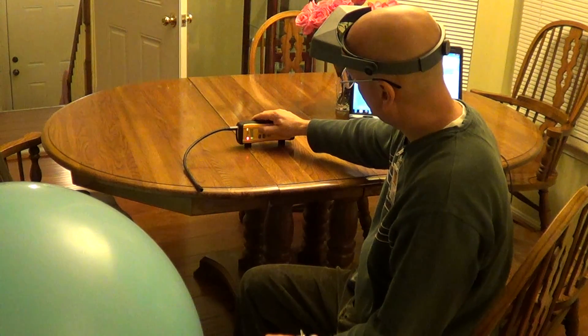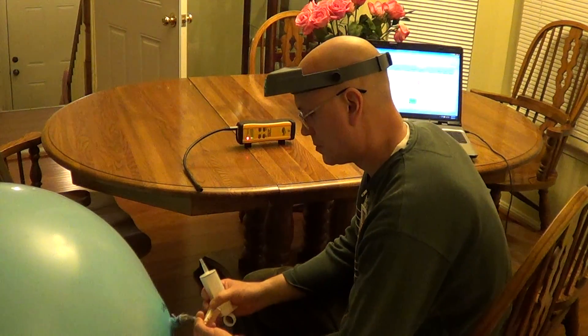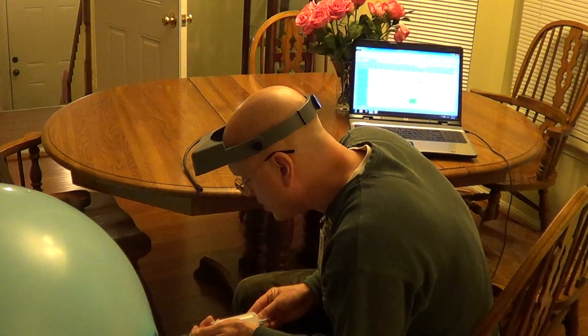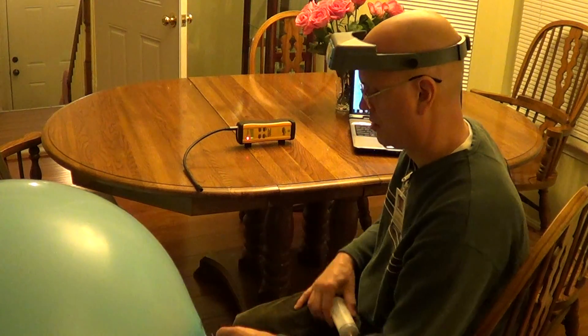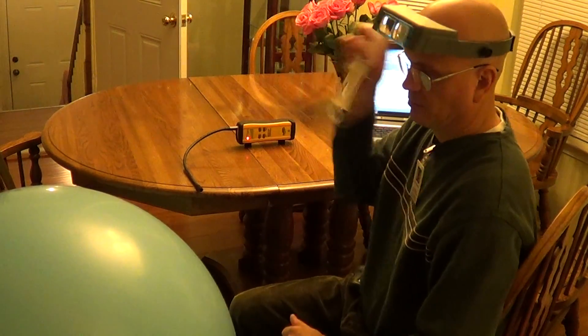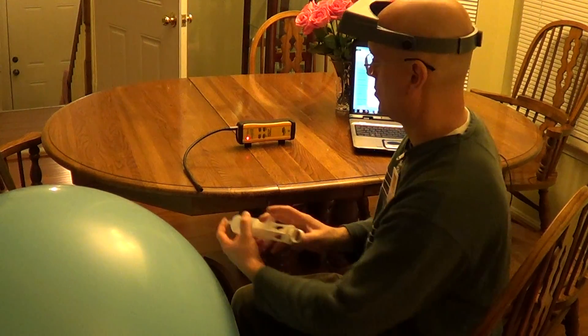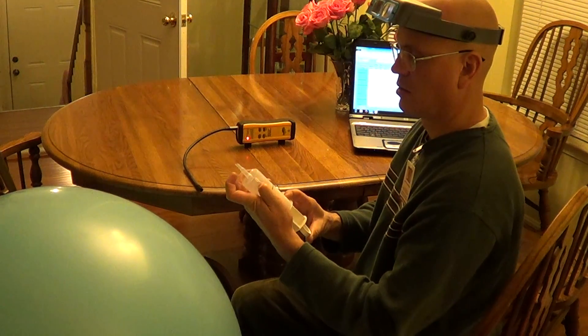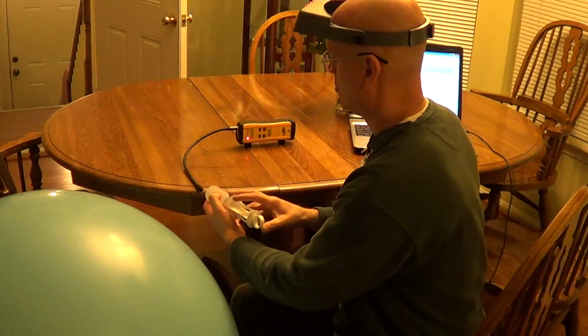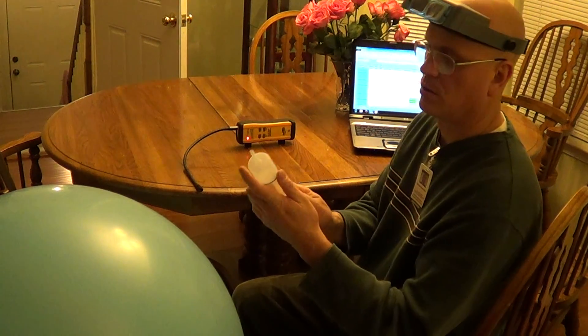Let's go on manual mode — I'm going to hold the button. 10 cc, add 90 of air, so we've got one part per million in the syringe. Then 500 parts per billion, then 250 parts per billion.